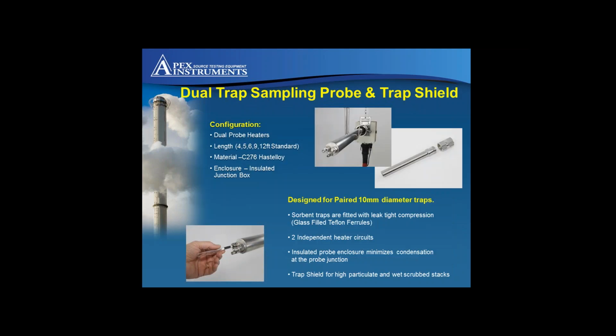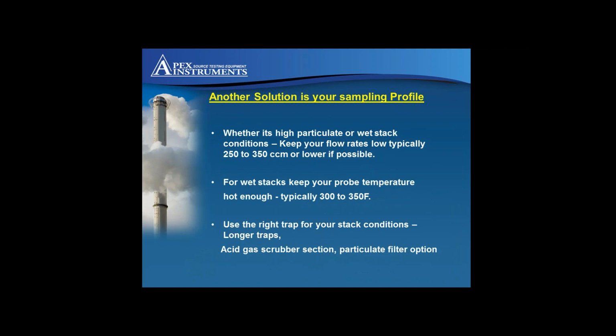As mentioned, it is always a dual trap probe and perhaps a trap shield assembly. Each side of the probe is identified as A and B. As a guide, always insert the lowest numbered trap into side A. Normal sampling and temperature of the stack is up to around 300 to 350 degrees Fahrenheit. The sample profile can be configured to suit the measurement location. It's an additional aid to a successful measurement program.